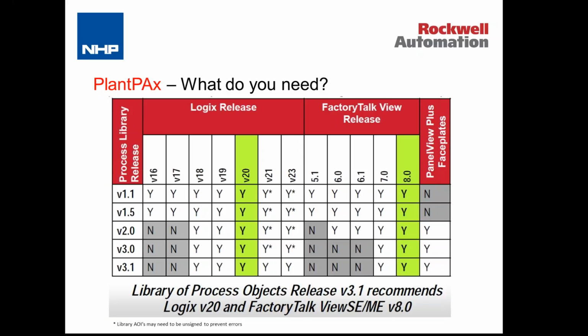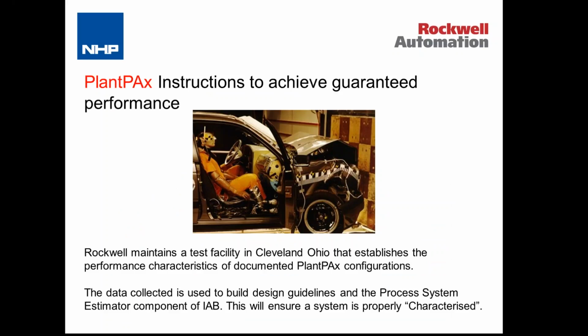And you'll notice that there are some compatibility constraints to be considered on version 21 and 23. And that's just to do with signing of the AOIs. And the signature may need to be removed if you're running those earlier versions, version 21, 23 of Logix. Now, importantly, I mentioned the Process System Estimator in Integrated Architecture Builder, and I mentioned the manuals that allow us to select and size the system. And the way we achieve that, this is all around, as the image suggests there, preventing an accident, preventing having a system where when you come to the point of commissioning or implementation, you find that it just doesn't perform the way it should. Now this is achieved.